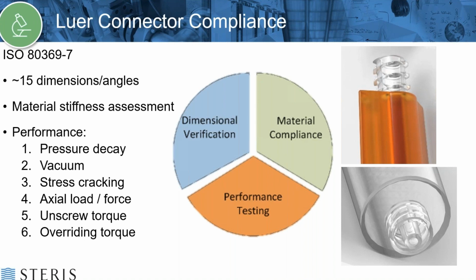Luer connector testing is another area of testing, and a Luer is a connector found on a syringe or a needle or a catheter. The first step is to prove dimensional compatibility with the ISO 80369 standard. You also must prove material compliance, and finally performance testing. And performance testing involves 6 different tests, including pressure decay, vacuum, stress cracking, axial loading, unscrewing torque, and clockwise overriding torque.